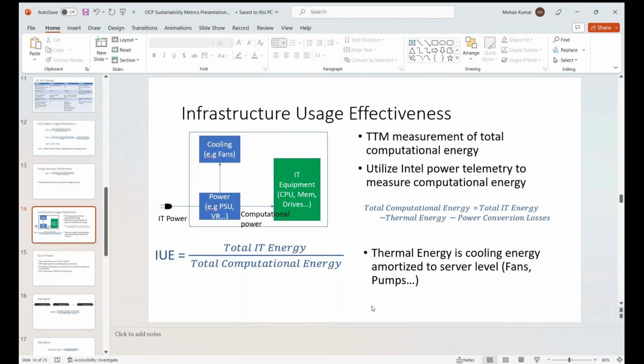But then if you want to measure the losses in such a system, they are occurring not exactly at a facilities level, but somewhere between the facilities and a server level, and we have to account for that, right? For example, that bus bar is not without its losses. The immersion cooling is not without its heat efficiency issues. So now what we have to do is introduce yet another concept to comprehend these things at an aggregate level.